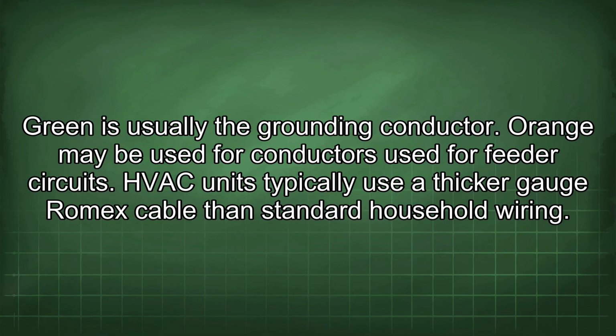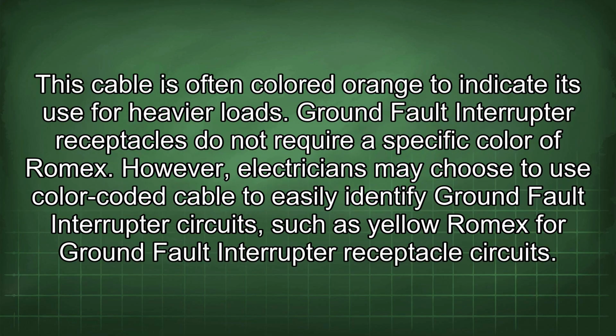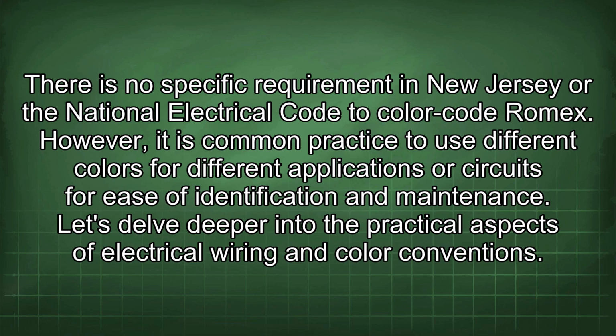HVAC units typically use a thicker gauge Romex cable than standard household wiring. This cable is often colored orange to indicate its use for heavier loads. Ground fault interrupter receptacles do not require a specific color of Romex. However, electricians may choose to use color-coded cable to easily identify ground fault interrupter circuits, such as yellow Romex for ground fault interrupter receptacle circuits. There is no specific requirement in New Jersey or the National Electrical Code to color-code Romex. However, it is common practice to use different colors for different applications or circuits for ease of identification and maintenance.